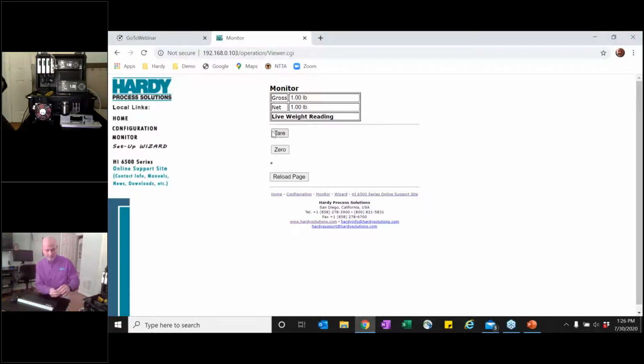This second test weight is a little 200 gram test weight, and we'll put that one on the scale. Now, 200 grams is going to be 0.45 pounds. So we've got 0.45 pounds, I'm sorry, 1.45, the 1 plus the 0.45, 1.45 here, and 1.45 on the monitor. So everything's reading the same. We can tell that these are all connected.